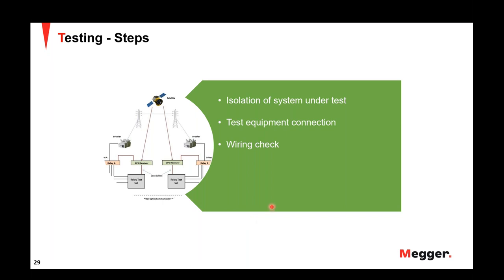The first thing we do after that is perform a meter test, right? When you perform a meter test, you inject currents and voltages on each end of the line, at all those relays, and you ensure the magnitude and phase angles are being metered correctly on the relay. What it tells you is that your wiring check is also done, and there are no issues with your wiring, like swapped phases or something like that. And then you would have to choose the types of tests you're going to run. What is the test mode or test method you're going to use, right? Is it a staged playback test method, or do you have complete files handy that you're going to run as a complete playback? And also, what kind of test scenarios are being used for testing? You would have to have all this ready when you perform this testing.